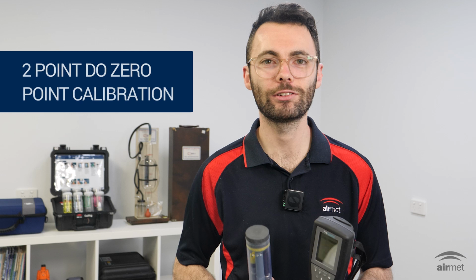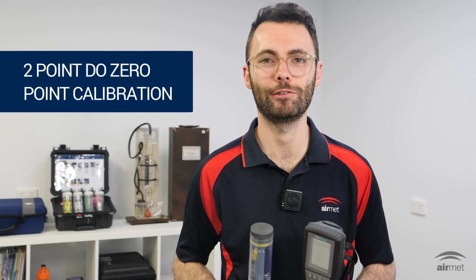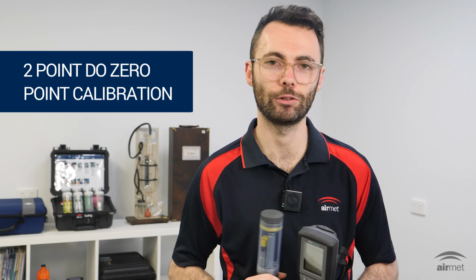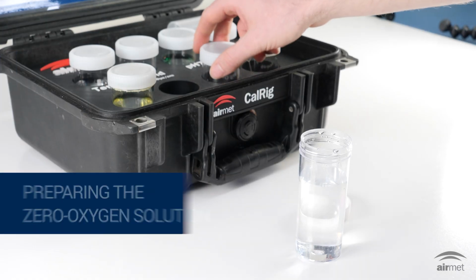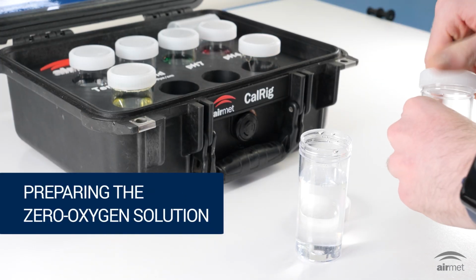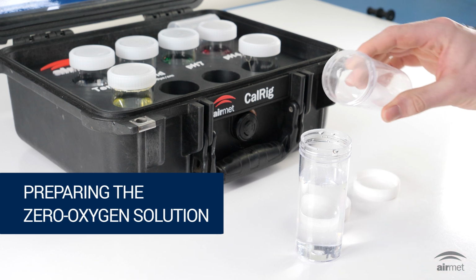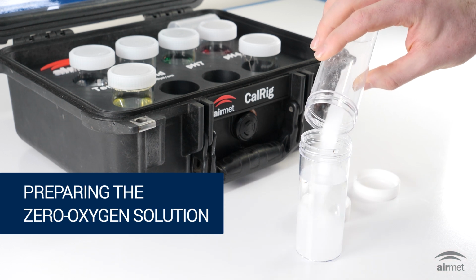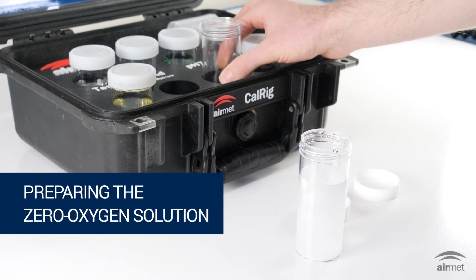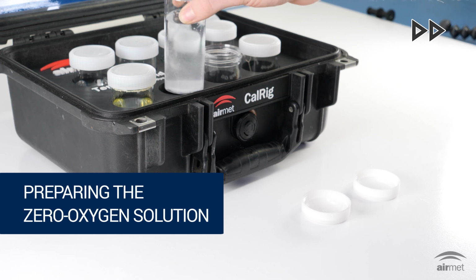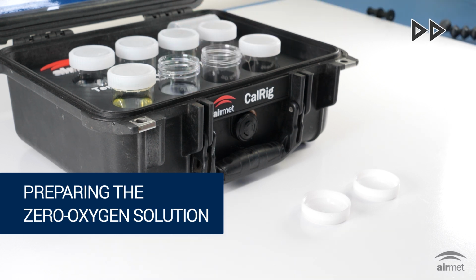Zero-point calibration sets the baseline for an oxygen-free environment. This is used when high accuracy is required at very low DO concentrations. A zero oxygen solution is made using a 2% sodium sulfite solution. The solution must be mixed with deionized water and left to sit for at least 60 minutes before use to fully scavenge the dissolved oxygen.